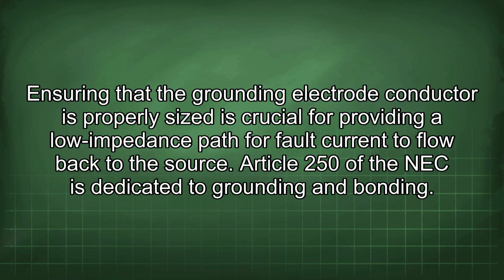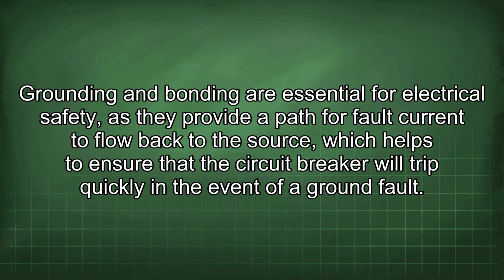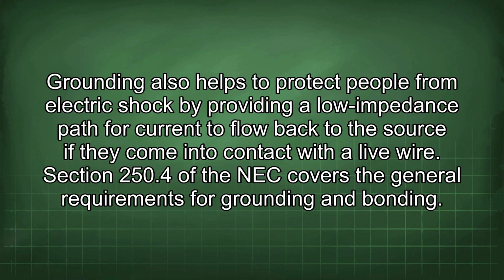Article 250 of the NEC is dedicated to grounding and bonding. Grounding and bonding are essential for electrical safety, as they provide a path for fault current to flow back to the source, which helps to ensure that the circuit breaker will trip quickly in the event of a ground fault. Grounding also helps to protect people from electric shock by providing a low impedance path for current to flow back to the source if they come into contact with a live wire.